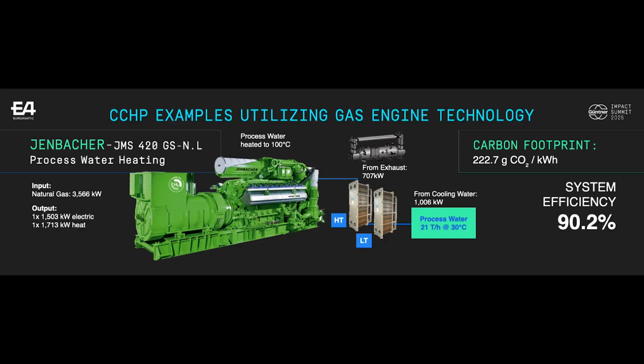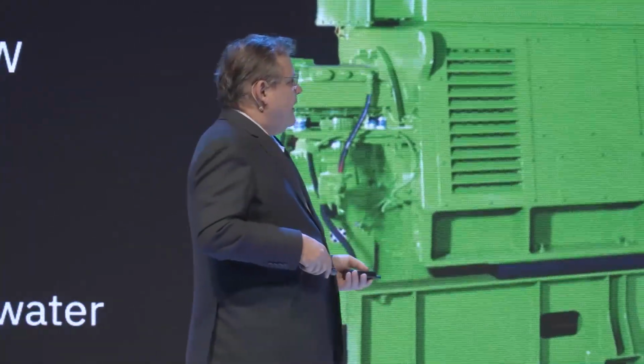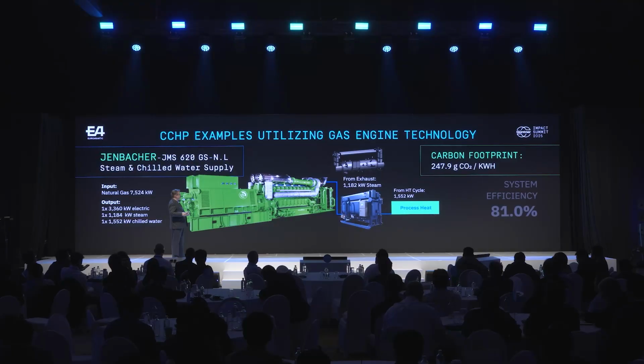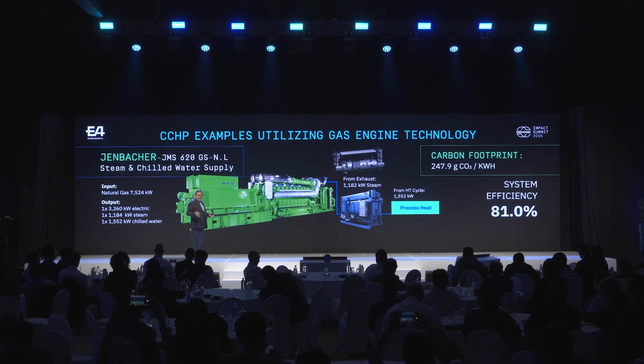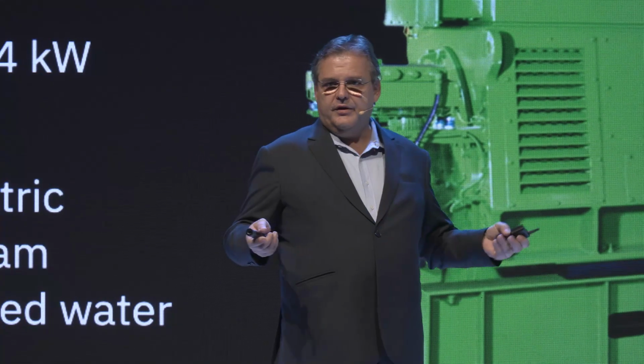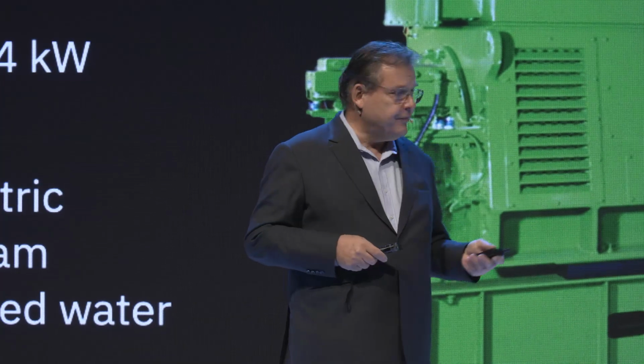some examples. I flipped just through it because of limited time. So we have process water on one side, everything coming out here, 90% efficiency, 222 grams. We have steam and chilled water with the jacket water. It's actually the most common one in Southeast Asia. We installed, I think, 9 sites with that. This is most often used in industry, especially when they need steam, and then the jacket water they cannot use, then they go in an absorption chiller.